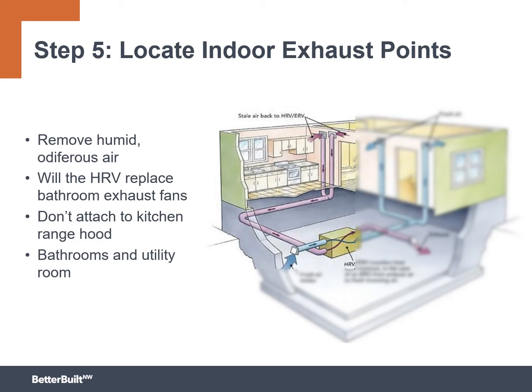Now, to that displacement, the question here: will the HRV replace the bathroom fans? It's a little bit more complicated than that. On the one hand, if you were to try to replace it entirely, the mechanical code does allow for a small continuous ventilation rate to satisfy the local exhaust requirement. But one of the problems with that is homeowners don't like fogging mirrors, right? And if you're trying to clear out the moisture in a bathroom after someone takes a shower, it takes a lot longer to defog that mirror with a low flow rate than it does with a higher flow rate for a shorter amount of time. So we want to think about that.